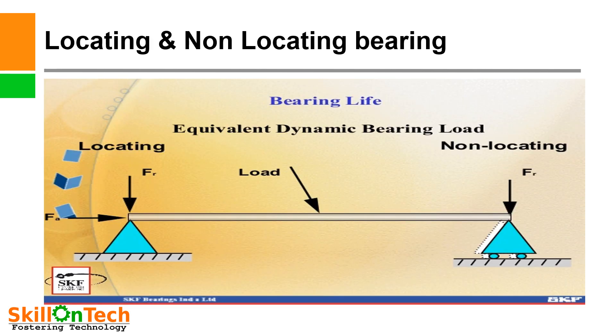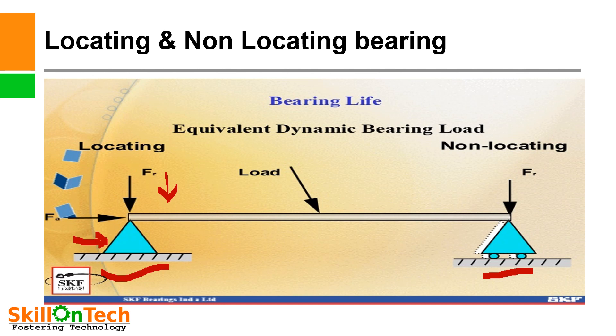Locating and non-locating bearings. In this picture you can see that the locating bearing is fixed with the housing location and must take both axial and radial loads — combined radial and axial loads. The other one is the non-locating side, which accommodates axial displacement of the shaft due to thermal expansion. If both bearings were made locating bearings, then thermal expansion would not be accommodated.